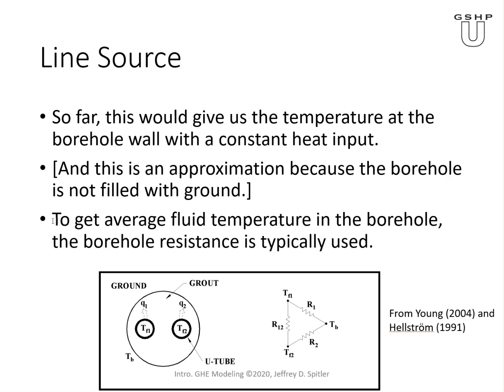Then we use a steady-state borehole resistance to get the temperature of the fluid. If you see here the temperature of fluid 1 and temperature of fluid 2, using the borehole resistance we can estimate the mean value of the fluid temperature. This is one network that's used — any network like this is also an approximation, but you see the borehole wall, a resistance between fluid 1 and fluid 2, and there's also some resistance indicating a possibility for short-circuiting.